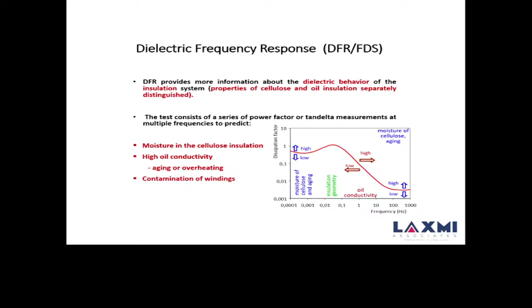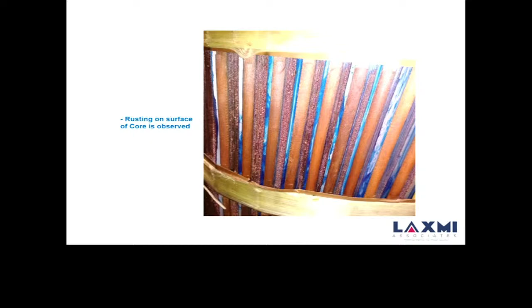Now what DFR, FDS, what I am talking about right now, measures the moisture in the insulation, that is one thing. If you have high oil conductivity, without taking the oil sample, you can measure the oil conductivity at site. Aging or overheating of the cellulose, that also you can see by having all the test parameters, dielectric parameters, and contamination of the winding. That means the winding is deteriorating or having some kind of partial discharge or some kind of tracking, all those contamination could be assessed by DFR.